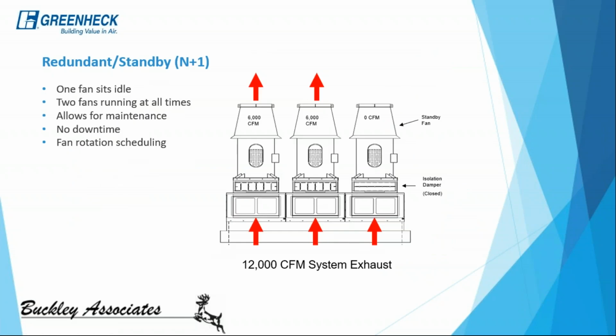Due to the nature and application of many of these laboratory fans, downtime's not really an option. These are critical facilities, so we need to build in some sort of redundancy. There are really 2 types of redundancy that are frequently used in all of these applications. The first type that we see here is going to be N+1 redundancy. This means that the system is going to be designed so that any one fan can go down for maintenance, or whether the thing crashes and breaks, the remaining fans are going to be able to handle the load.